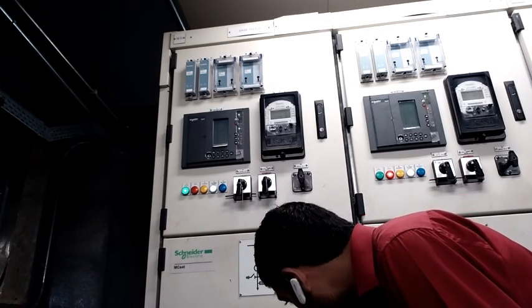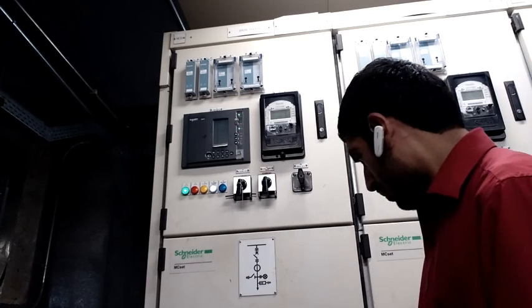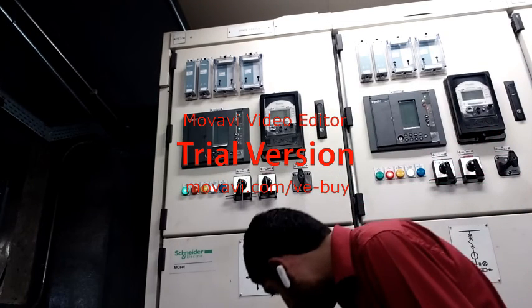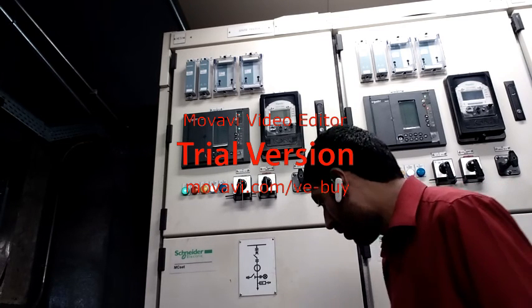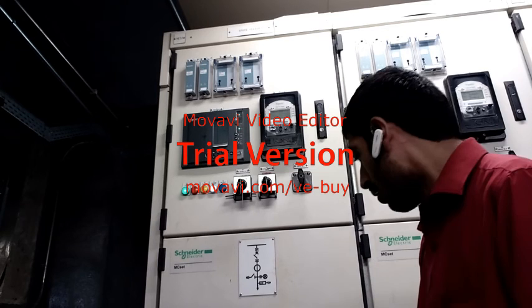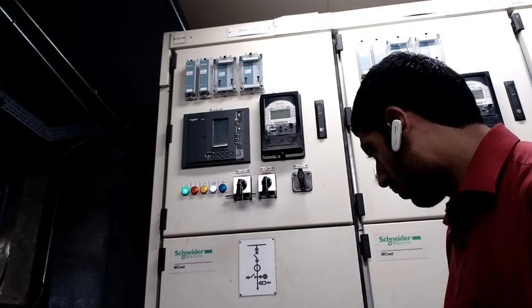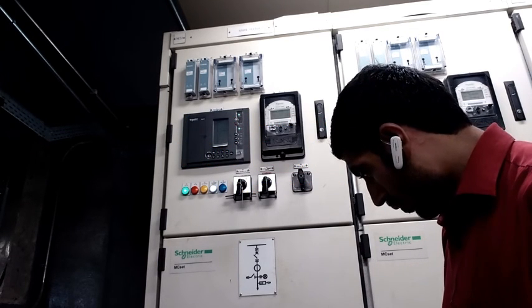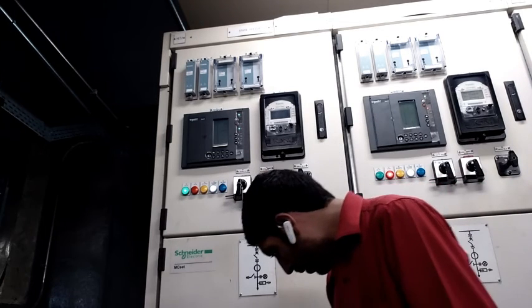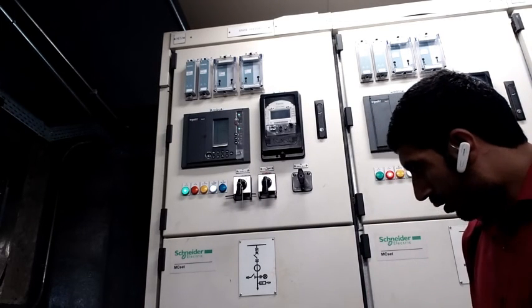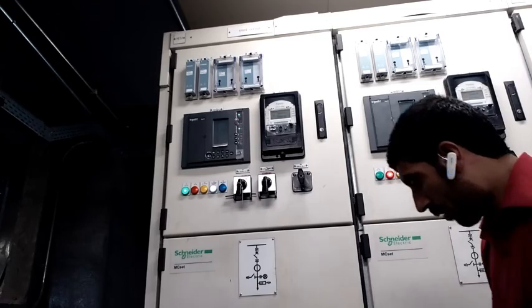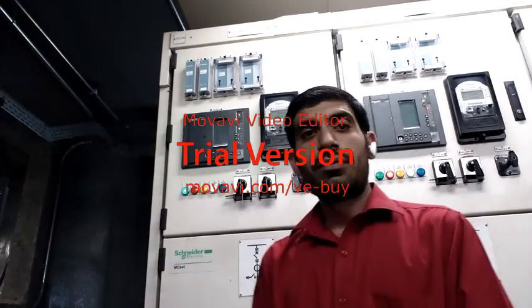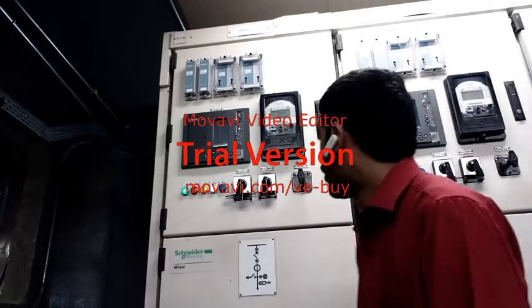17.5 kilovolts, and the rated current of this breaker is 630 amps, and frequency is 50 hertz or 60 hertz. You can choose one of these two values for this breaker. And this is made by Schneider, and we also have one switch used for protection of this breaker. So all these things I want to explain to you.